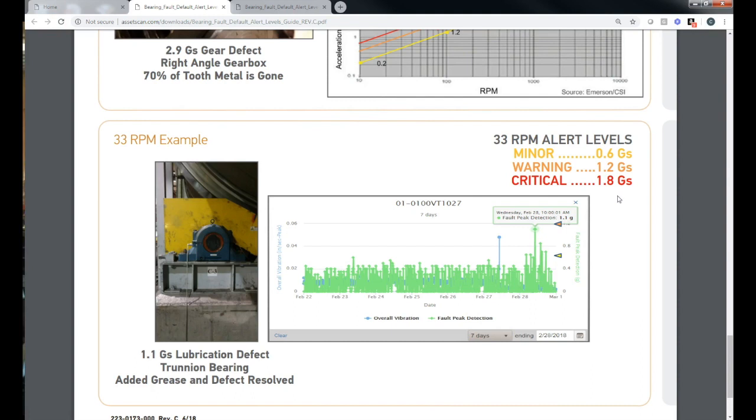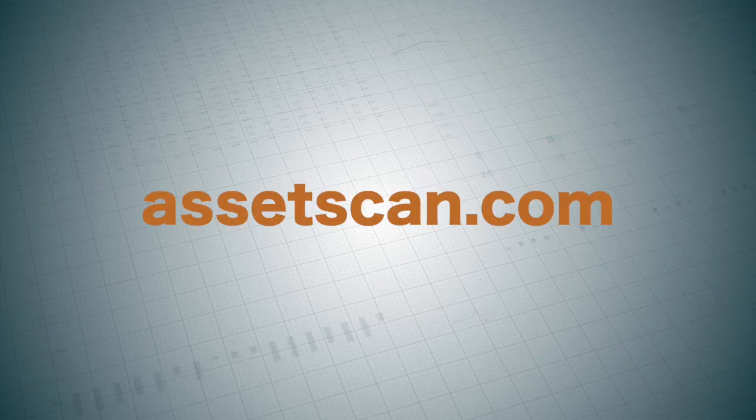Interesting point here is that the asset scan has a store and forward capability. This is a remote location in a steel building, and the customer was concerned the cellular would not get out. We went ahead and deployed this, knowing that he could pull that box out of that steel building, get reception, and the data would flow. In reality, the text message was able to get out from inside this building. It doesn't need much, doesn't need the full strength that you need for voice, and we'll retry to get that data out.